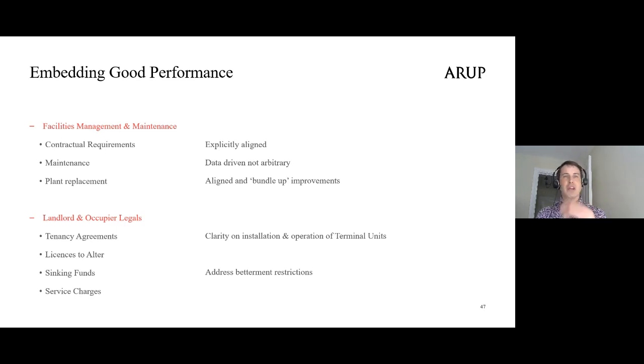The next point is the landlord-occupier relationship, touched on by Karina. It's important to note that even with the initial NABERS UK rating being base building, that covers heating and cooling demands for tenancy areas. In the UK, tenants often have responsibility for how terminal units in their spaces are operated, installed, commissioned, maintained, and controlled. Danny mentioned simultaneous heating and cooling - a classic issue we see time and again in open plan offices, where terminal units fight each other, one heating, one cooling, wasting energy and adding to discomfort. When we've addressed that, both energy use and complaints have dropped significantly.